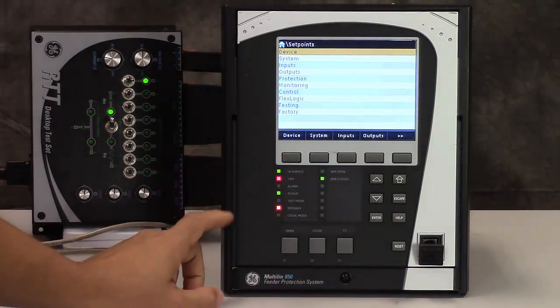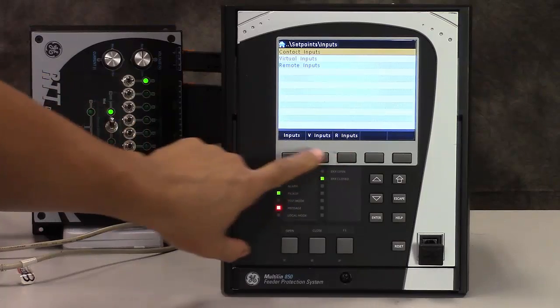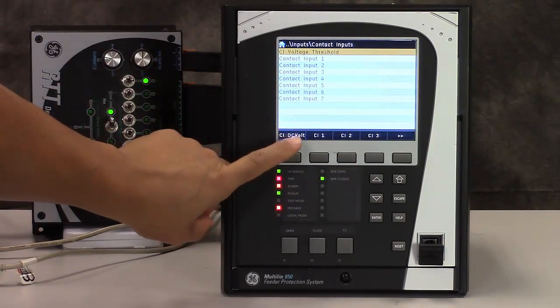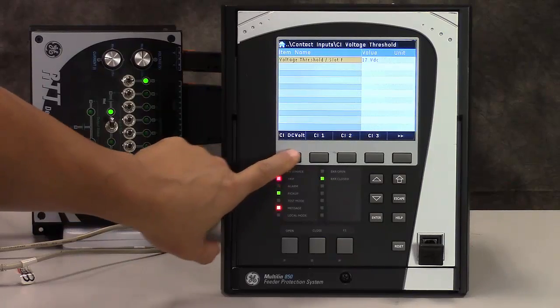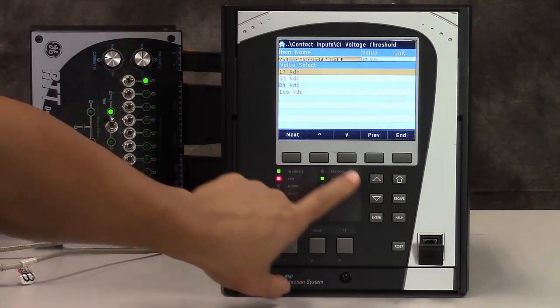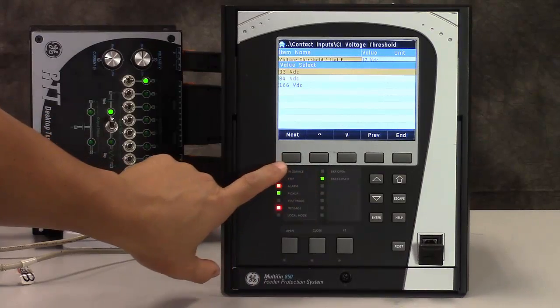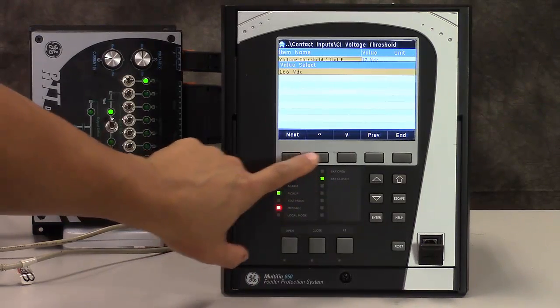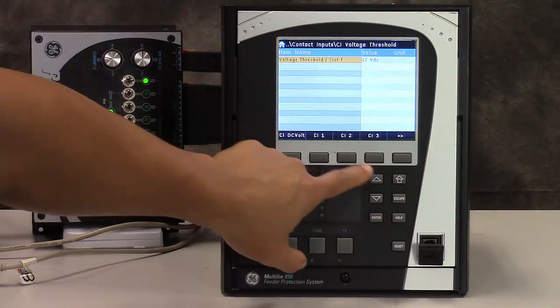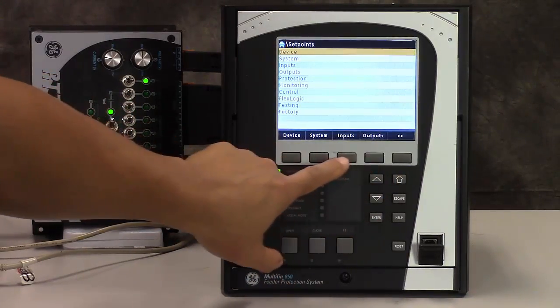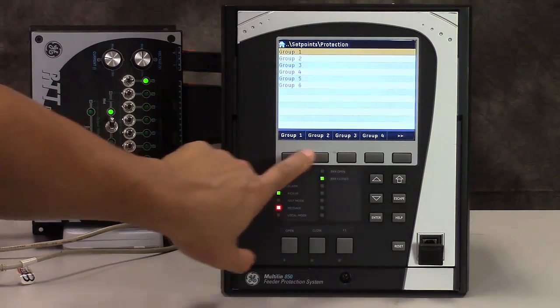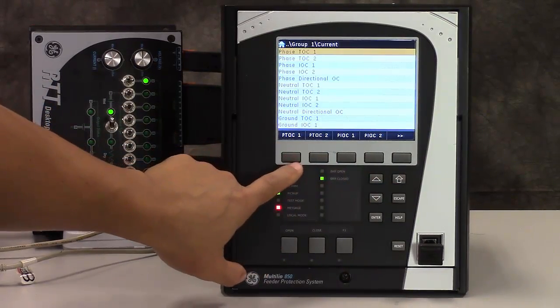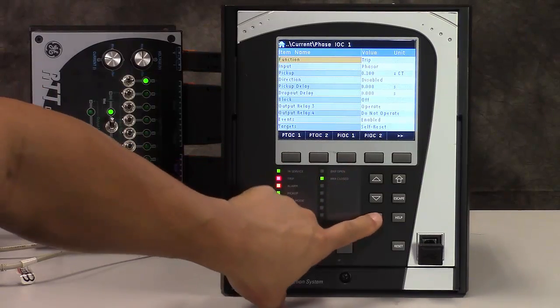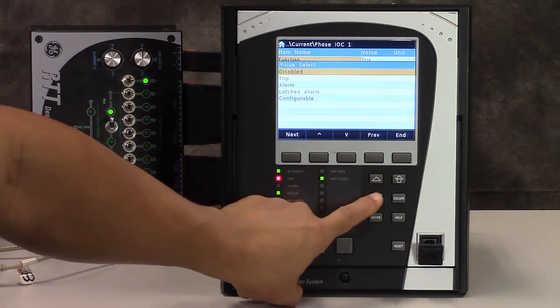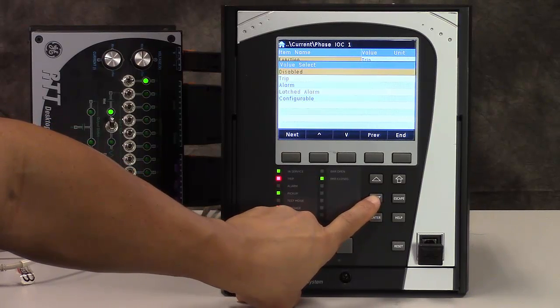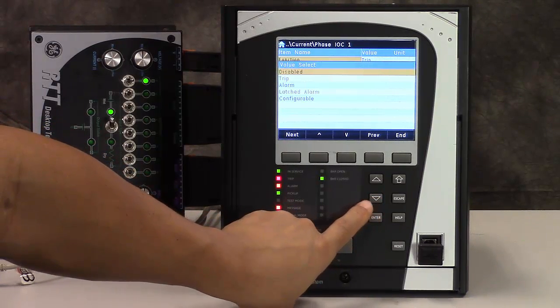From the set points, we can also check other settings. For example, set the contact input voltage threshold. There are 4 levels we can pick. And also we can set the protection elements. Going to protection and selecting group 1, we can set the phase IOC pickup, and we can enable the function by choosing trip, alarm, latched alarm, or configurable.